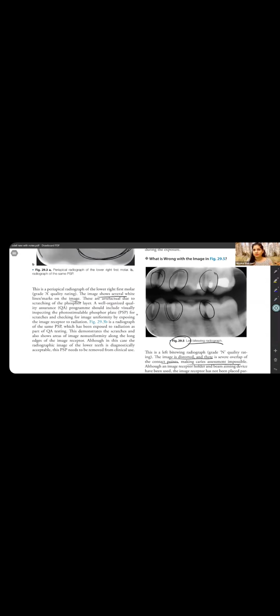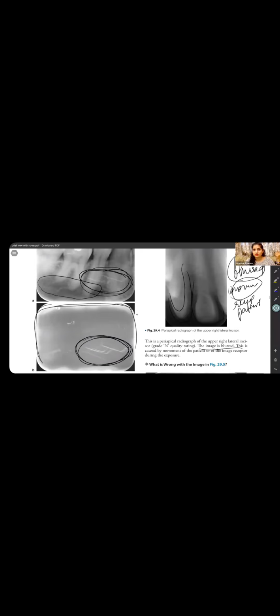And I tried my best to create a parallel with the film-based radiography. I hope that made sense to everyone. So with the wrong side exposed, we draw a parallel with the film side, and then with your bite wing also, the sensors and the film also, you get the bite wing errors. Similarly, the horizontal angulation was incorrect. Then the scratch marks: if the emulsion gets peeled while processing, before you put it into the processor, if the emulsion gets peeled off, then you get the scratch marks.